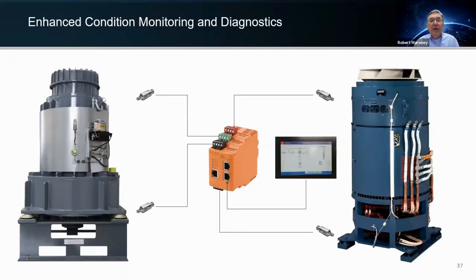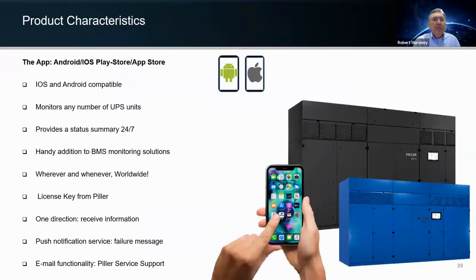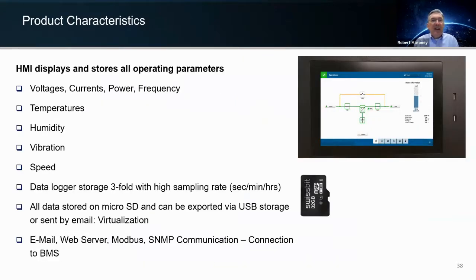Enhanced condition monitoring. So we know what the speed is of our MG, what the status of our MG is. We know exactly how much speed and stored energy is in that flywheel energy storage device. So we know exactly how much ride-through time we have to mitigate your power quality issues. It has a very, very detailed HMI that takes you from component temperatures, voltage, currents, power, to input, ambient humidity, speed of the flywheel and the MGs, and data loggers. We have a 3-level data logger that logs data at 1 second, 1 minute, and 1 hour. It holds the 1 second for an hour, and actually 3 hours, and it holds the 1 hour up to 18 months. So you have a true record of what the system is seeing.